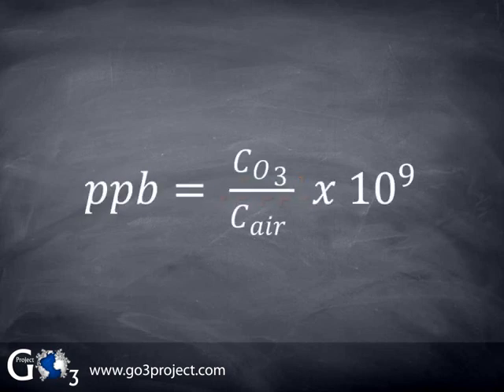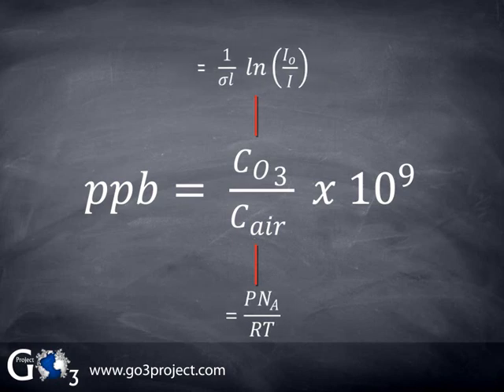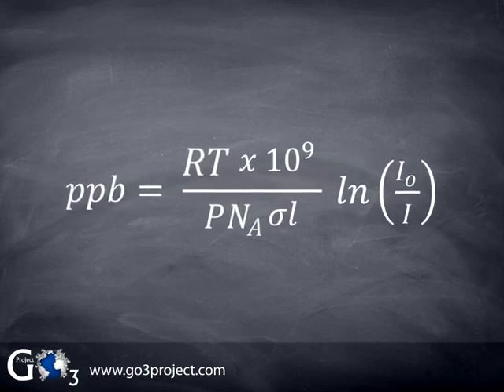Let's now combine the two equations, the Beer-Lambert law and the ideal gas law, to obtain a single equation for calculating ozone mixing ratio in PPB. This is the equation used in all modern ozone monitors to calculate ozone. Since the effects of temperature and pressure on air density are included, ozone monitors that use this equation are said to be temperature and pressure corrected.